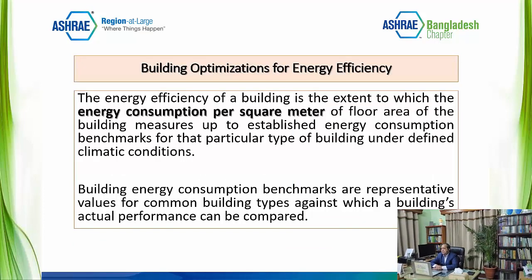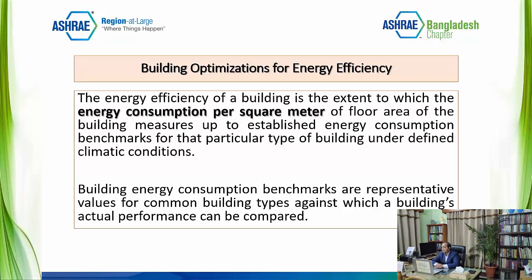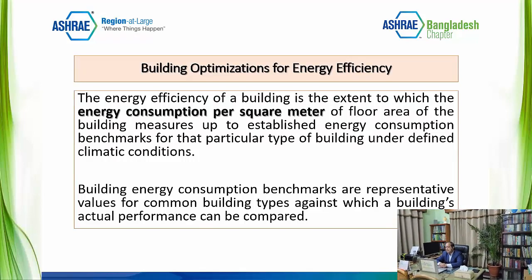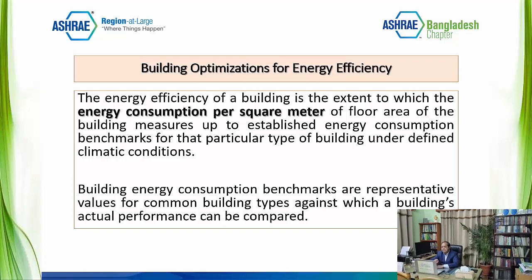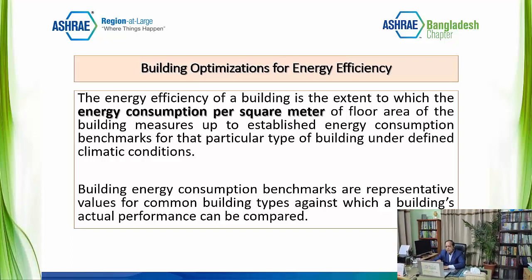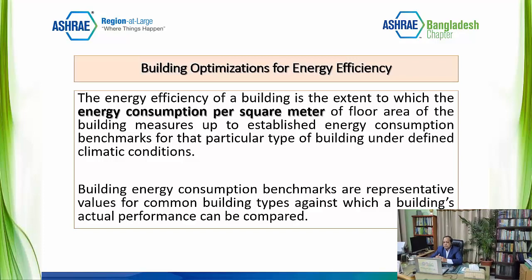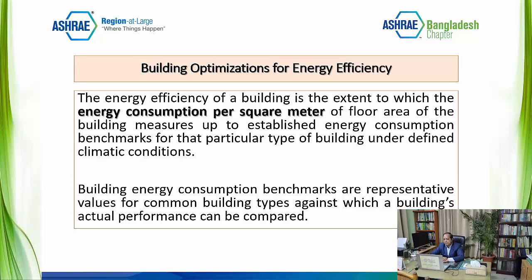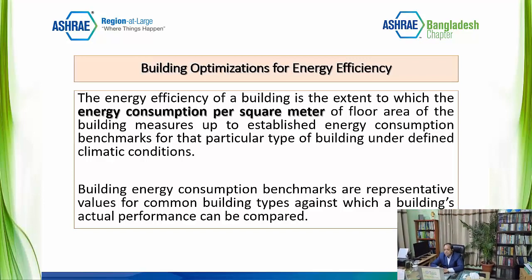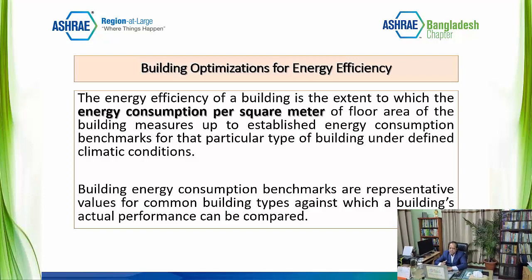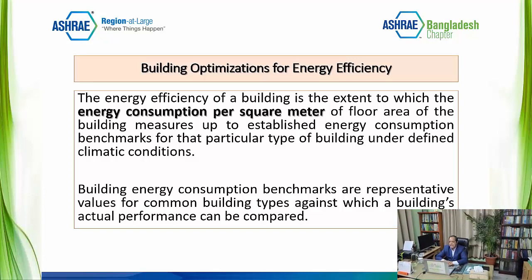So we can only achieve that if we understand the concept of building optimization. What is building optimization in terms of energy? In the ASHRAE standard or any other energy-related standard, it will tell you how much energy you should use per square foot or per square meter for cooling, the cooling load, right? If you use more than that, then you are not optimizing the building. So we have to know this number first: what is our cooling load, energy load amount, for a particular area in a region, in a city, or in a weather, and then how much we are using, to compare with that.